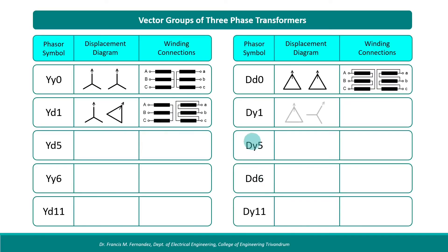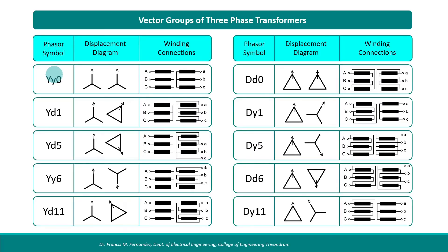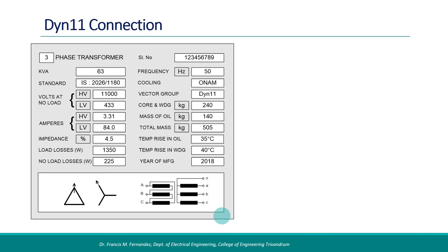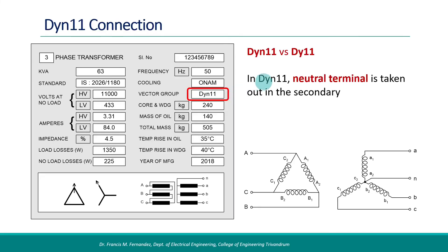Here we have a summary of all the vector groups discussed so far. The phasor symbol, the displacement diagram, and the connections in each case are shown. Going back to the transformer nameplate seen earlier, the vector group is given as DYN11. The difference from DY11 is that it has the neutral point of the secondary brought out as a terminal, and the connection diagram is changed accordingly — the neutral point is added. All the other things including the phase relationship remain the same.